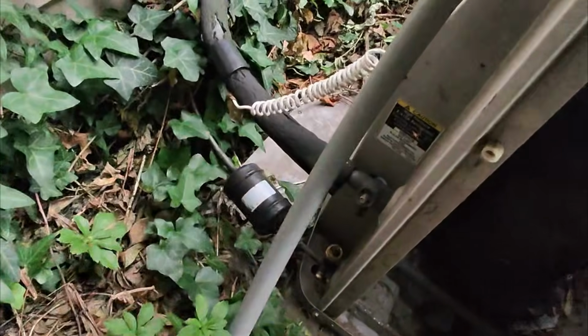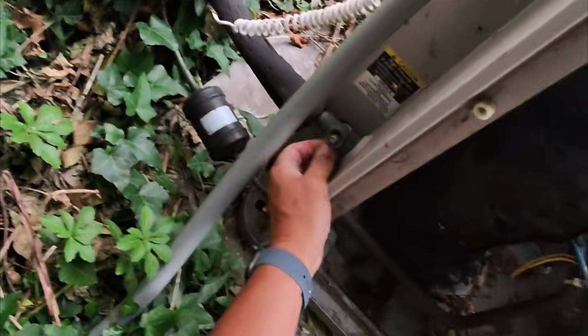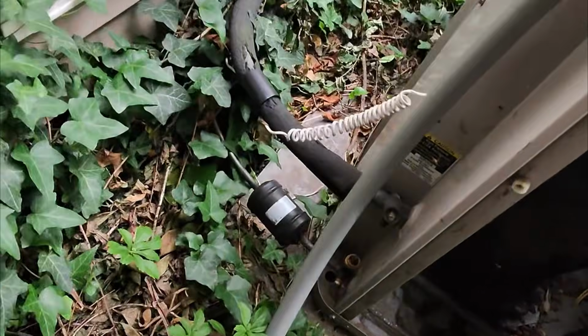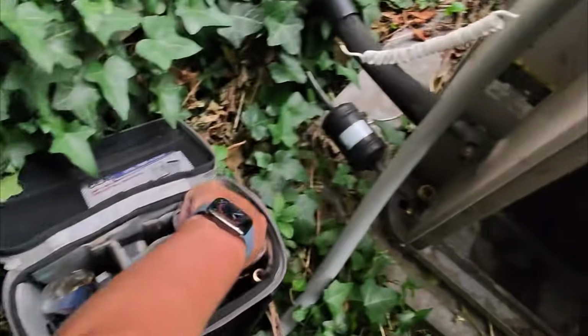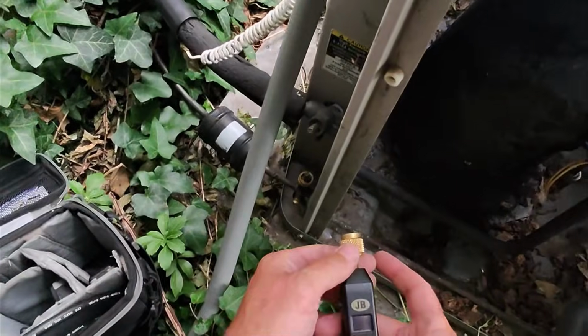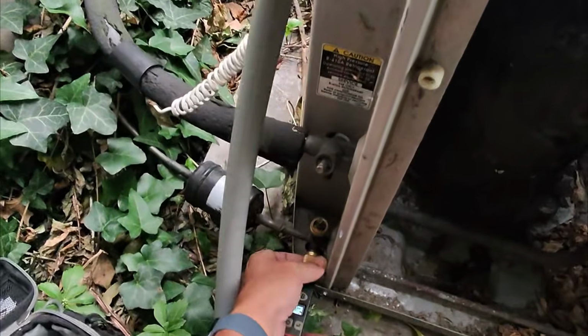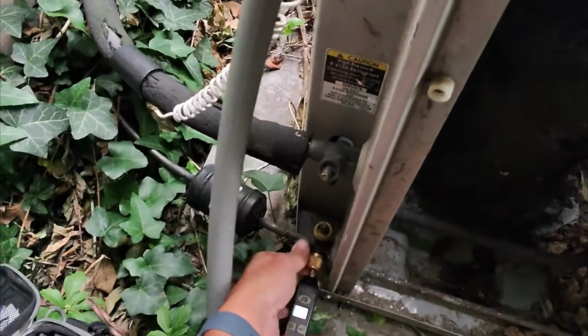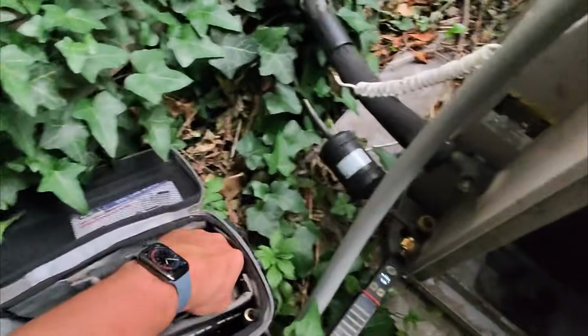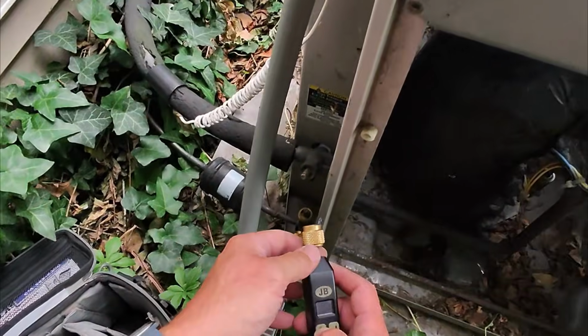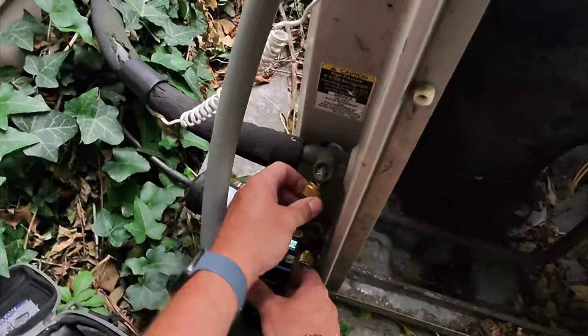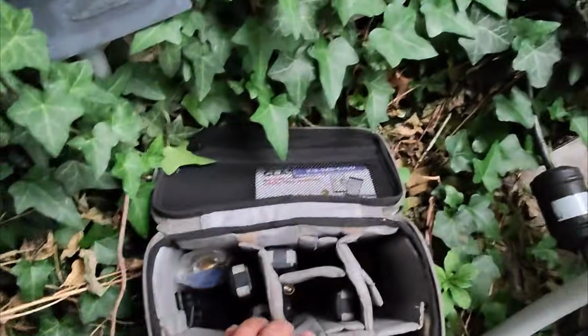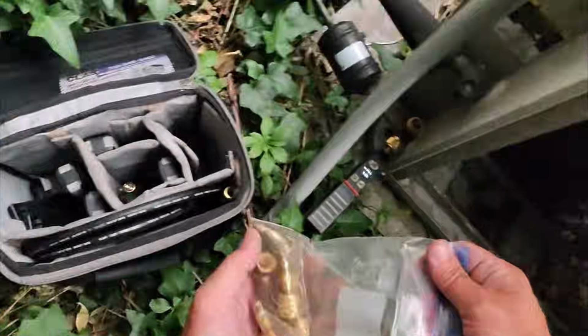I'm going to start outside by pumping down the refrigerant. If I push down on the contactor, I should be able to do that. Let me just get my pressure probes set up. I'm using the JB Climate Class probes. There's that one there. Here's the other one there. Oh, we made a little adapter on there. I knew it.